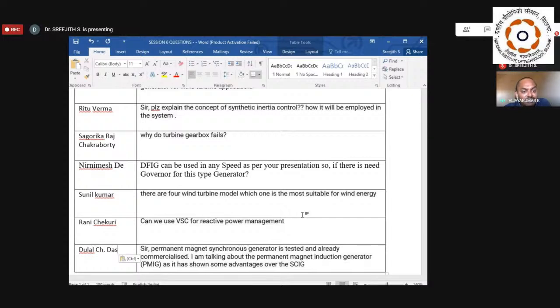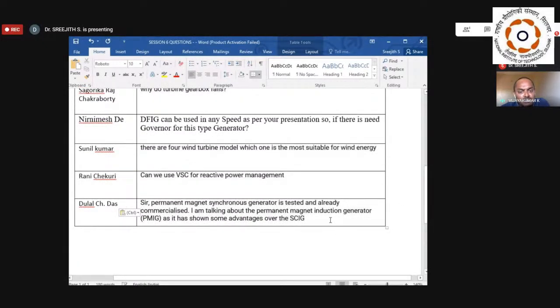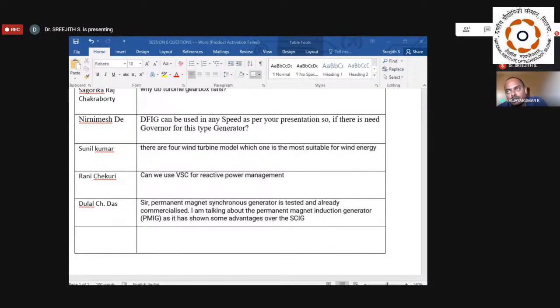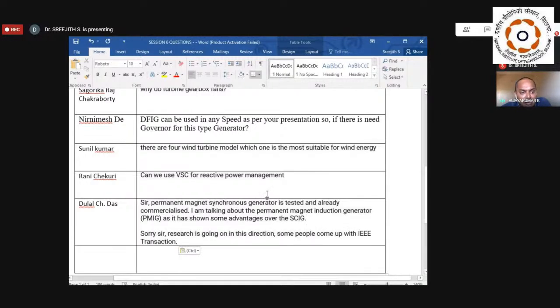Why am I saying DFIG is not for any speed? It operates at subsynchronous and supersynchronous speeds, 30% below and 30% above, so you get a wide speed range. There are four wind turbine models; which one is the most suitable for wind energy? It depends upon the size and the location. For megawatt turbines, permanent magnet synchronous generators and doubly fed induction generators are the preferred candidates. For small scale turbines, 5 kilowatt or 10 kilowatt, permanent magnet synchronous generators are the best suitable candidate. For earlier wind turbines of 100 or 200 kilowatt, if you don't want to use power electronic converters, then squirrel cage induction machines are the best candidate. So it depends upon the location and the size of the wind turbine.